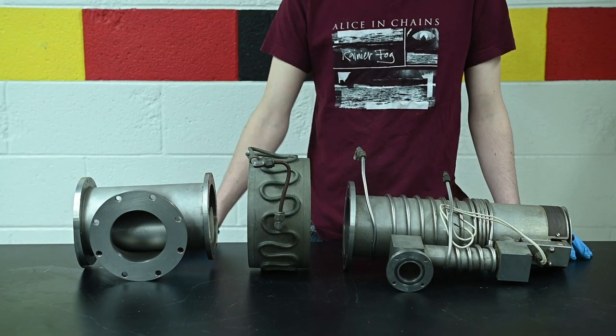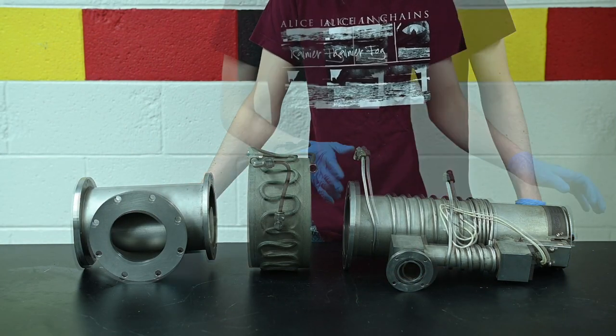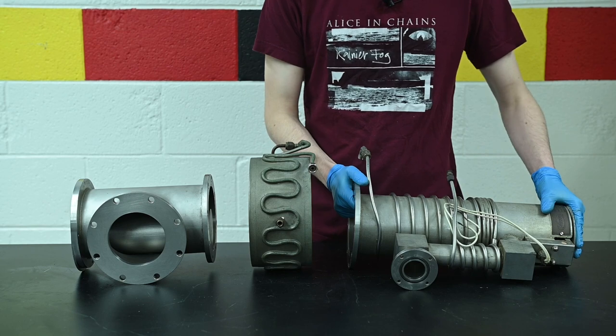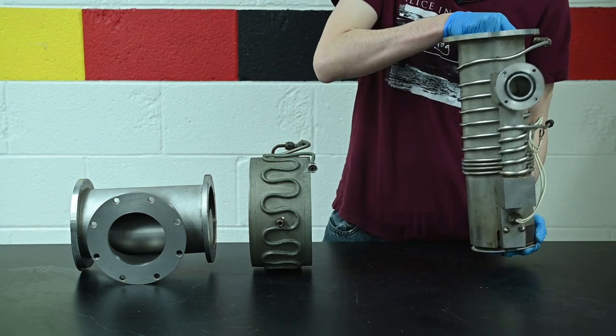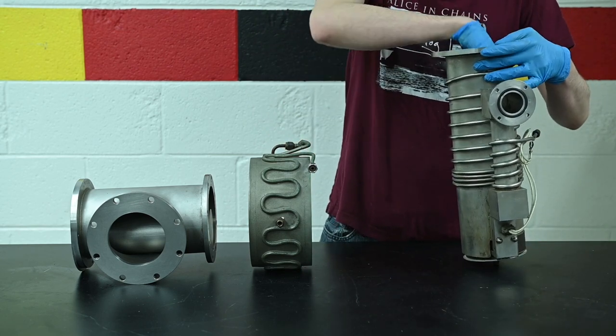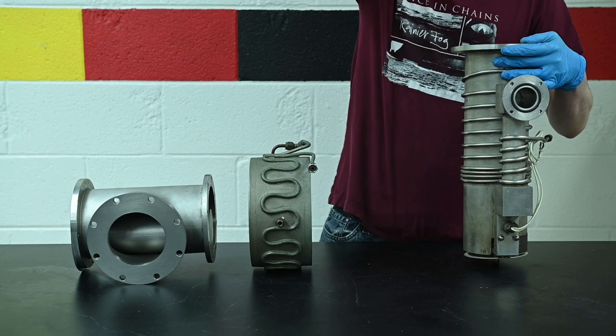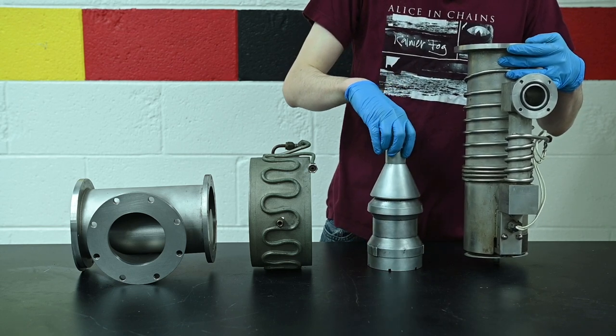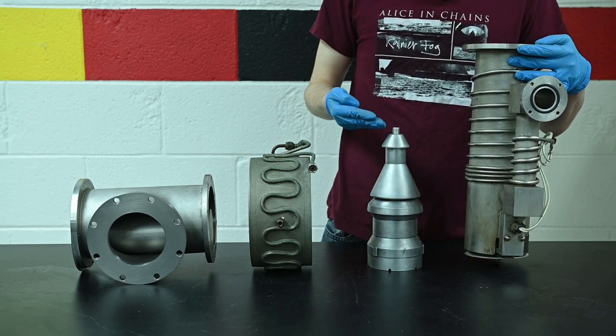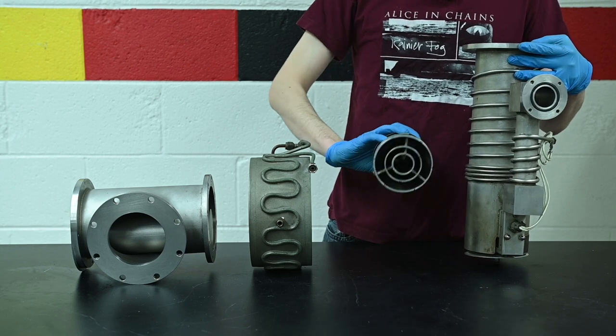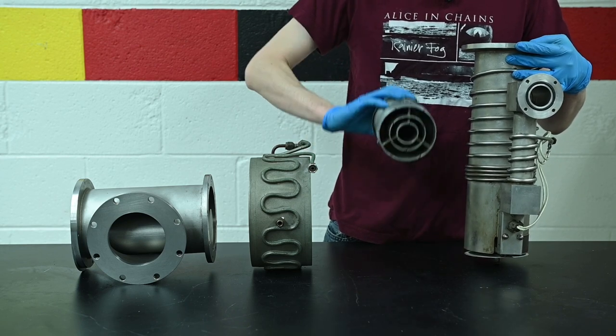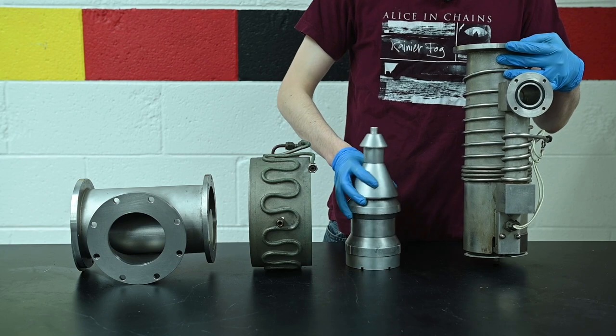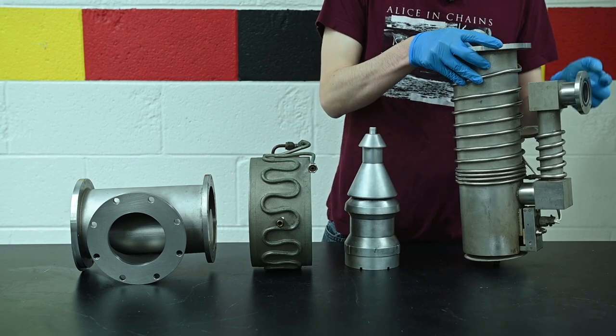We have now removed the diffusion pump and have disassembled it. Here we see the main body of the diffusion pump. Inside is the Christmas tree assembly. The Christmas tree is hollow and has many external conical structures known as chevrons. When oil is vaporized in the base of the diffusion pump by the heat of the diffusion pump mantle, it travels upwards and is smoothly redirected back down into supersonic jets by the chevrons.